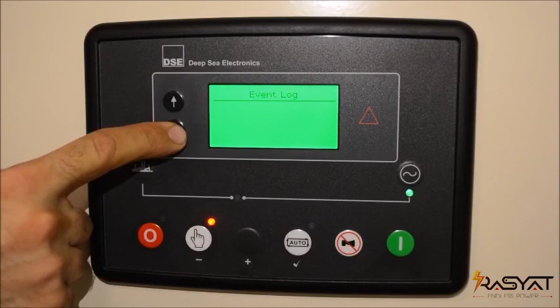amps. For status, press and hold the black down arrow until you see status on the screen. Now we have the generator voltage, frequency, amps, kilowatts in one screen.